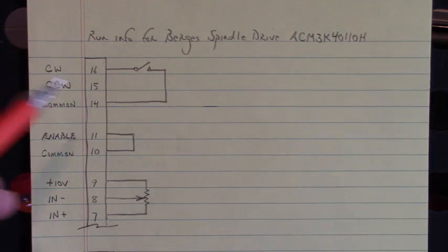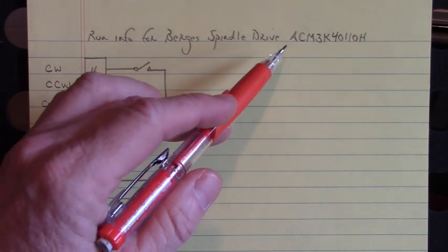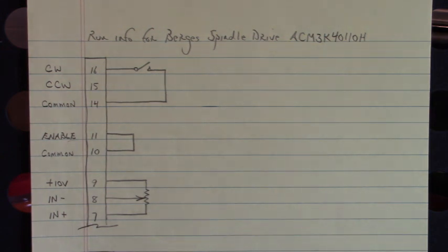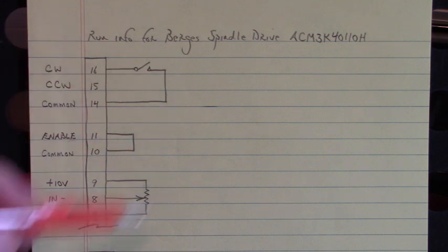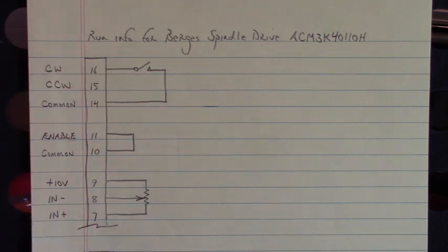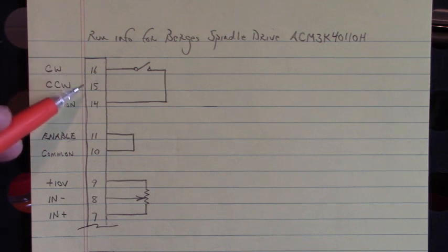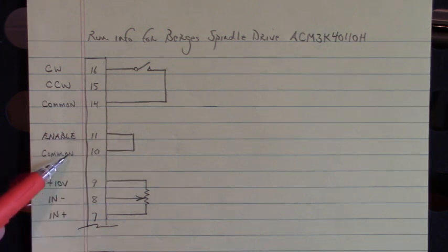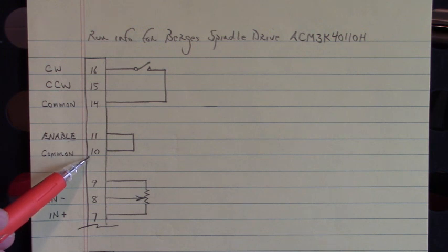Now here, we have the Berges Spindle Drive, model ACM3K40110H. And displayed here is the control hookups to make that spindle drive run that spindle motor. Here we have on terminals 16 and 15, clockwise and counterclockwise, and terminal 14, common. Down here, we have the enable on terminals 11 and 10.